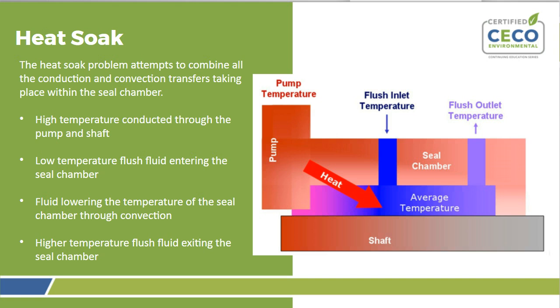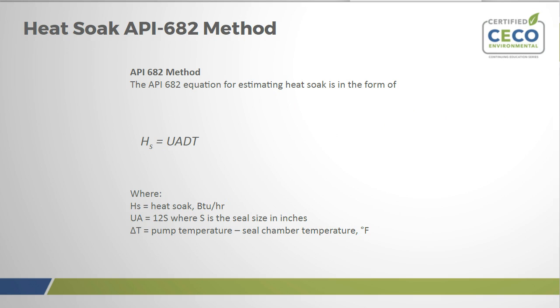So there's all sorts of things going on in the seal chamber itself. You have conduction from the pump itself, the metal components of the pump. Low temperature fluid entering the pump from the heat exchanger. Fluid lowering the temperature of the seal chamber through convection and the circulation of the fluid itself, and then higher temperature fluid that's then exiting that seal chamber. So it's a rather complex heat exchange question, but API 682 has a rather rudimentary, very simplistic calculation for trying to figure that out and to see how many BTUs you're actually going to require to keep your seal chamber at a certain temperature.